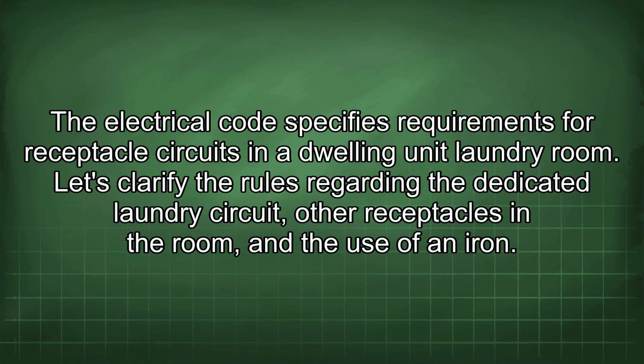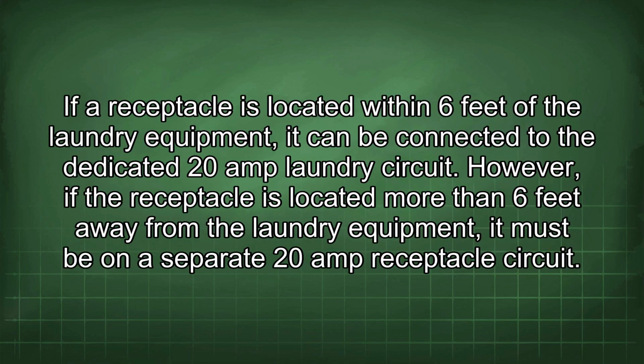The electrical code specifies requirements for receptacle circuits in a dwelling unit laundry room. Let's clarify the rules regarding the dedicated laundry circuit, other receptacles in the room, and the use of an iron. If a receptacle is located within 6 feet of the laundry equipment, it can be connected to the dedicated 20-amp laundry circuit. However, if the receptacle is located more than 6 feet away from the laundry equipment, it must be on a separate 20-amp receptacle circuit.